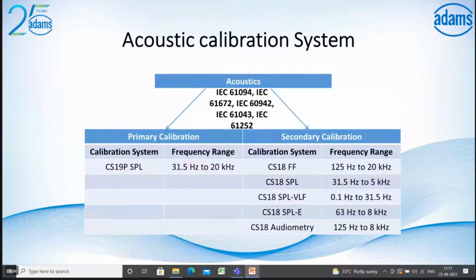And now acoustic calibration systems, which is according to the IEC standards, the International Electrotechnical Commission: IEC 61094, the method for the calibration of working standard microphones; IEC 61672, the method for the calibration of sound level meters; IEC 60942, the method for the calibration of sound calibrators; IEC 61043, the method for the calibration of sound intensity microphones; and IEC 61252, the method for the calibration of noise dosimeters. And Spectra is offering acoustic calibration for both primary and secondary calibrations.